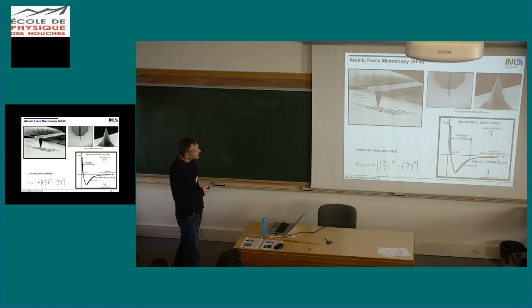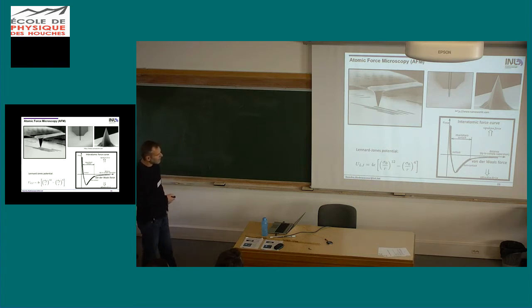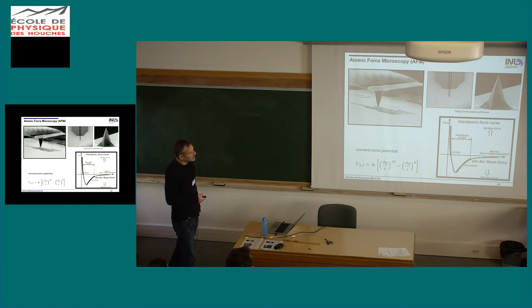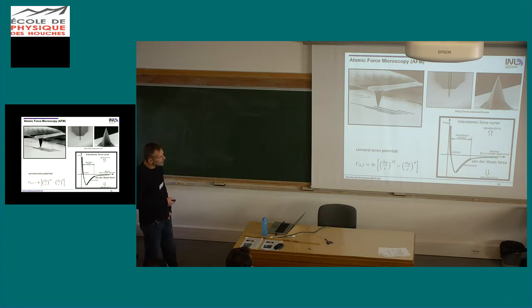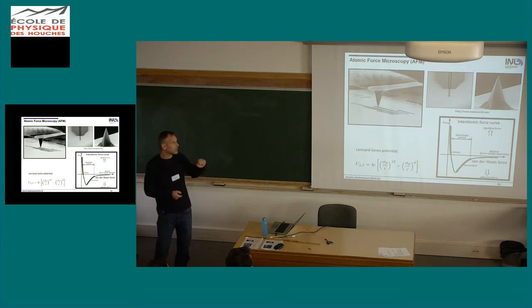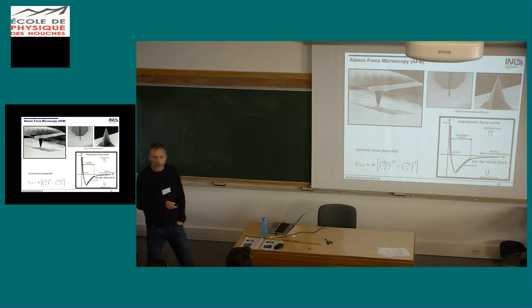And what governs the interaction between the sample and the tip is this force distance curve. So let's start here. If you're far away with your tip from the sample, there's of course no interaction. Now you get closer and closer, then at some point the van der Waals forces become important. These are attractive forces between tip and sample atoms. And at some point, if you go too close, you get a lot of attractive forces, but then it converts into repulsive forces. So that's when you go very close and you get essentially a Pauli repulsion between the electron clouds of the tip and the sample atoms. And this part of the curve you can model, or approximate, by the Lennard-Jones potential, which is a phenomenological way to describe these forces.